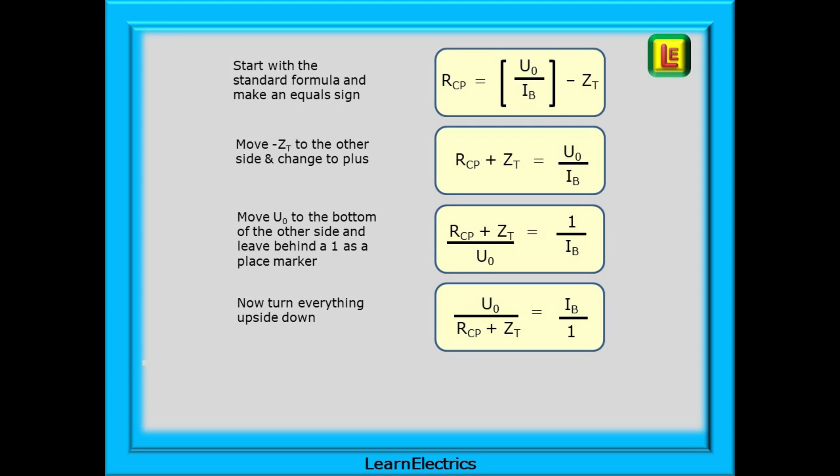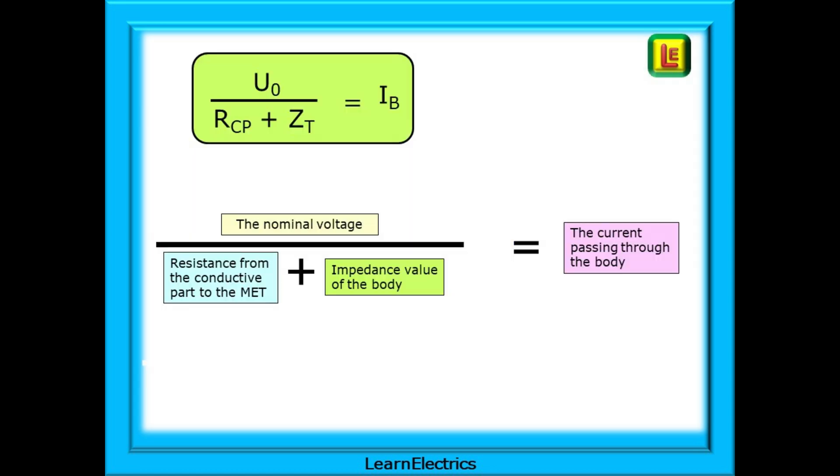Follow these steps and pause the video if you need to. Start with the standard formula and make an equals sign. Now move minus ZT to the other side and change the minus to a plus. We can move U0 to the bottom of the other side and leave behind a 1 as a place marker. Now turn everything upside down to arrive at the finished formula as shown at the bottom. This formula is telling us to do what? It is telling us that if we take the nominal voltage and divide this by the resistance from the conductive part of the MET and the resistance of the body added together, the result will be the value of current passing through the body. Ohm's law again. Voltage divided by resistance equals current.